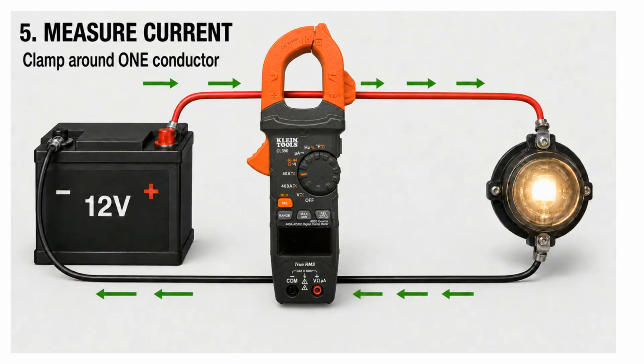The fifth use is measuring current with the clamp. Current is the amount of electricity flowing through a wire. It is measured in amps. Unlike a basic multimeter that must be connected into the circuit, the CL390 can measure current by closing its clamp around one wire. For the small DC circuit shown here, turn the selector dial to the 40A position. Select DC current and zero the meter according to the CL390 instructions before taking the reading.